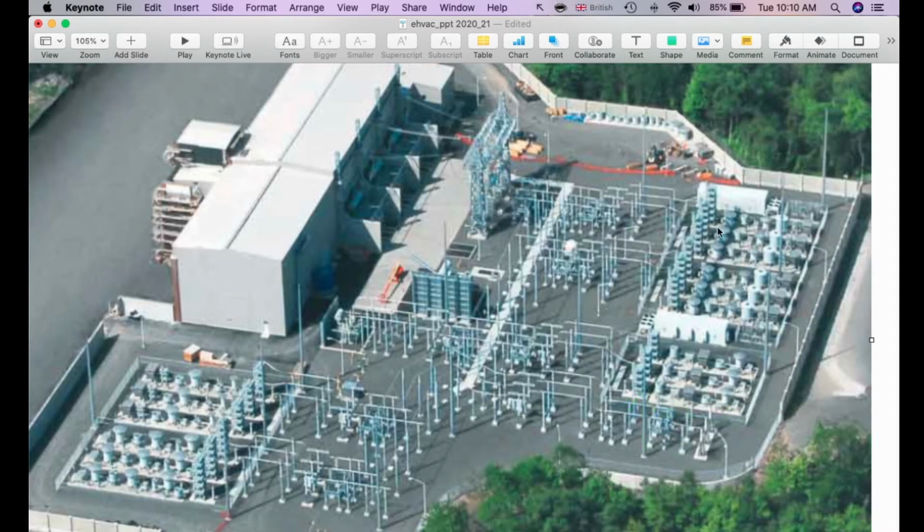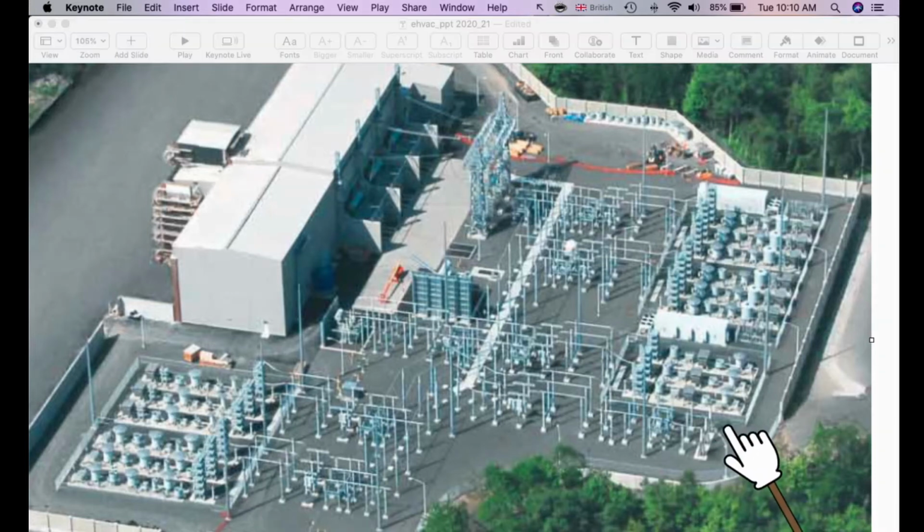And naturally, why are so many filters required? Because a variety of harmonics are produced on the AC side and similarly on the DC side. So this side you may consider this is AC side, okay, and this is DC side. So two poles are here, and here there are three sets of circuits, so R, Y, B phase. This is here positive and negative pole, okay. So consequently, in this scheme a variety of frequencies are being eliminated in every phase, right? So there are current harmonics, there are voltage harmonics, okay.